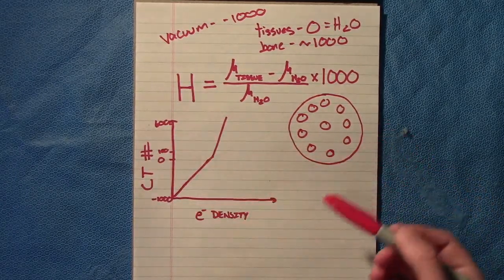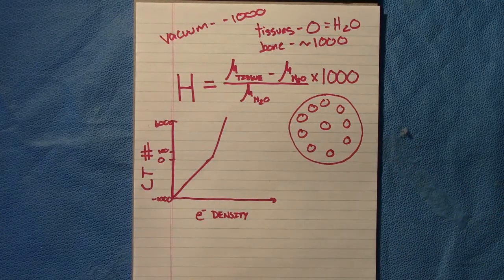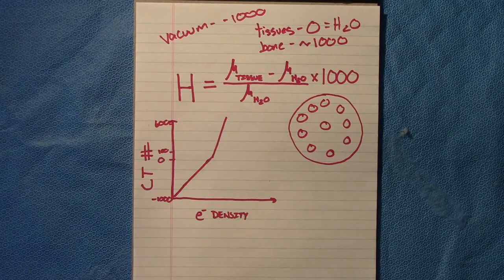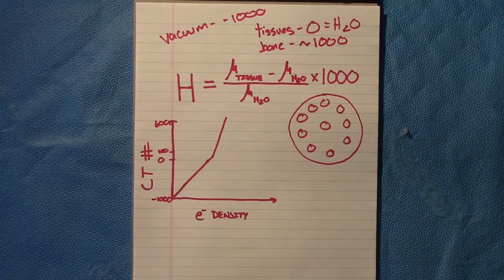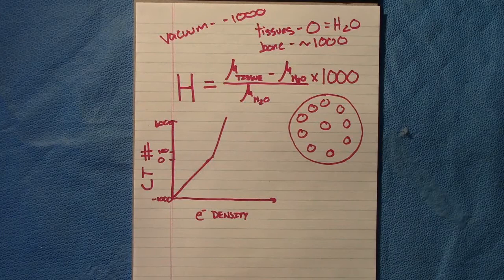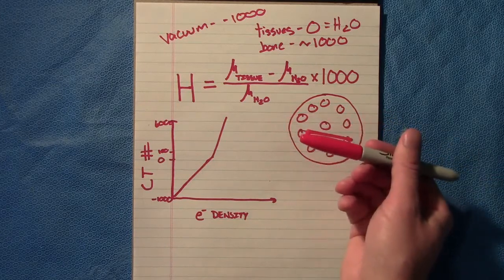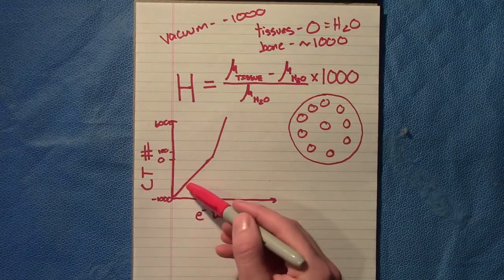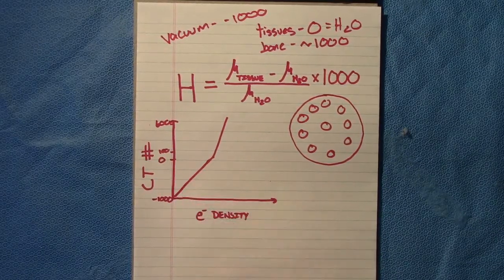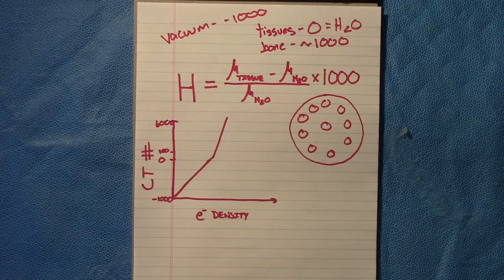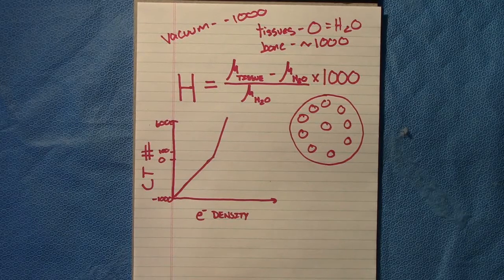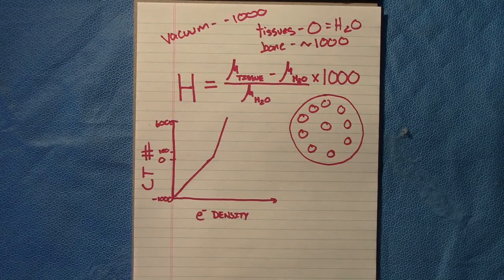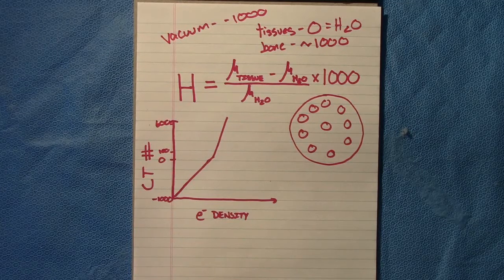In our treatment planning system, we are going to put this graph into whether it's BrainLab or Eclipse or Pinnacle, whatever system we're using. That is going to look at the structure, that CT, and what that beam is going through. It's going to say, 'Okay, I'm going through lung. Lung has this CT number. This CT number has this electron density.' It's then going to use that electron density to help with the probability of Compton interactions and overall account for the heterogeneity correction for that plan and that CT specifically.